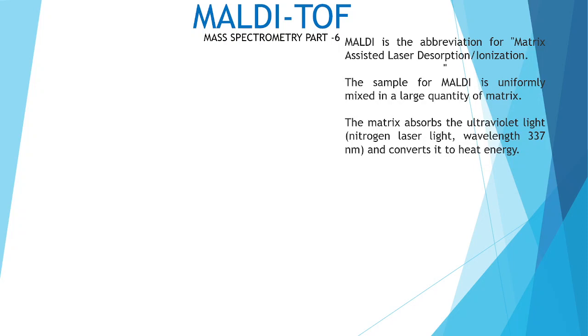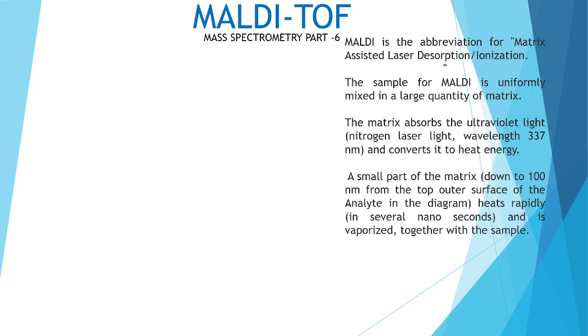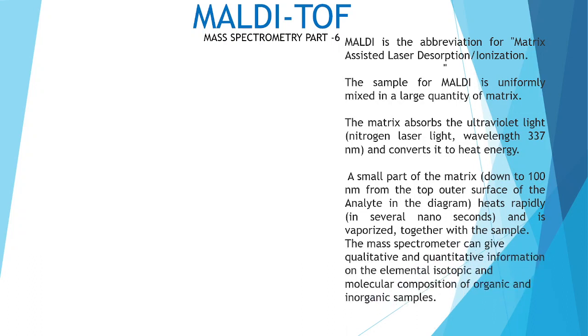The matrix absorbs ultraviolet nitrogen laser light at a wavelength of 337 nanometers and converts it to heat energy. A small part of the matrix, down to 100 nanometers from the top outer surface of the analyte, heats rapidly in several nanoseconds and is vaporized together with the sample.